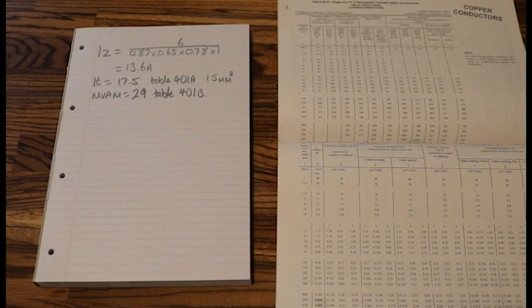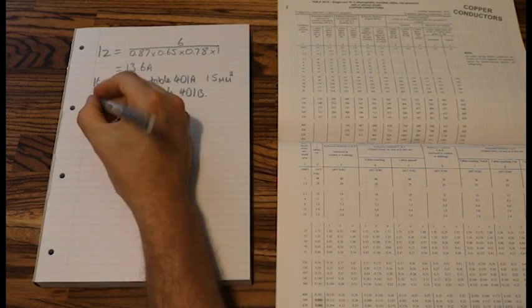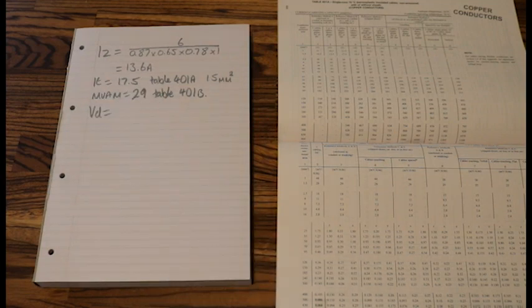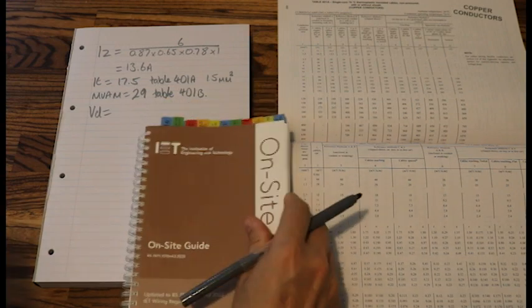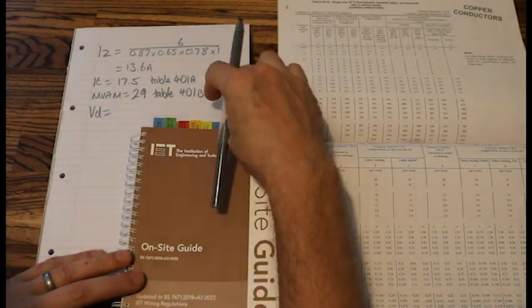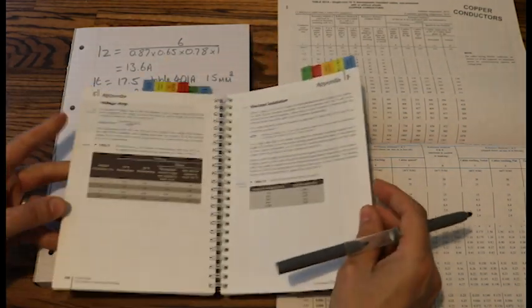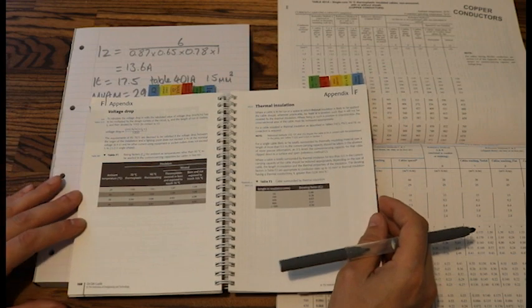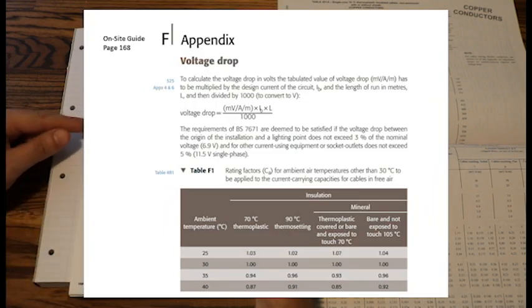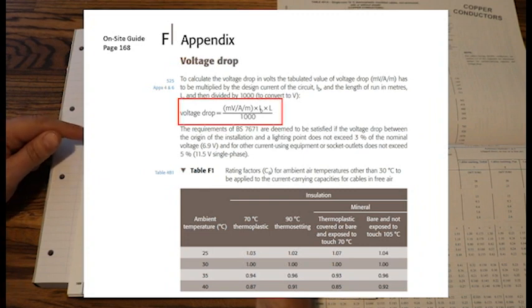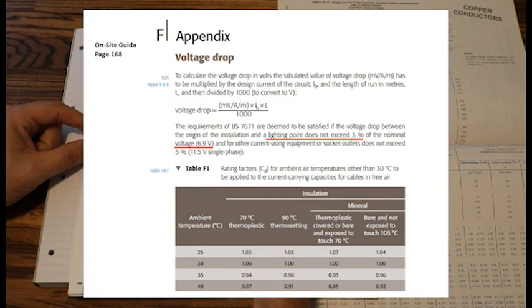Now we need to do our Voltdrop formula. So for our Voltdrop formula, if we have a little look at our onsite guide and we go to our Voltdrop tab, so Voltdrop in the onsite guide, page 168, gives you your formula here. Voltdrop formula is mV/A/m times IB times length, divide 1000. And below it, this paragraph here says for a lighting point, which ours is.